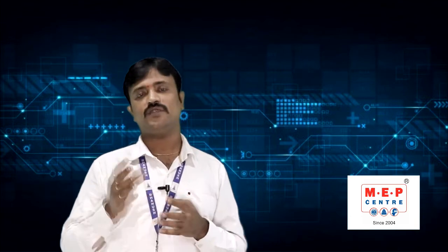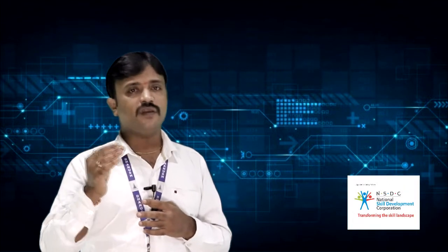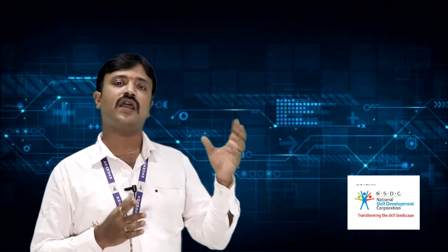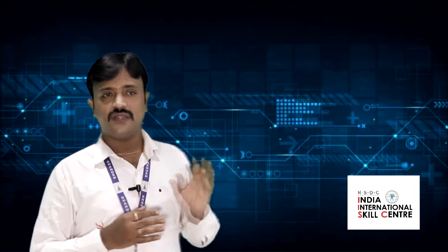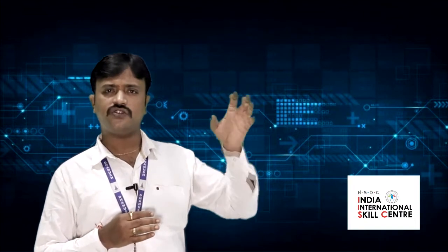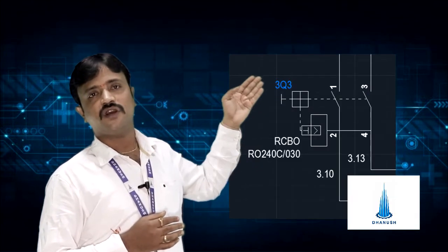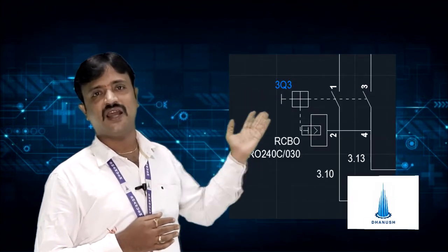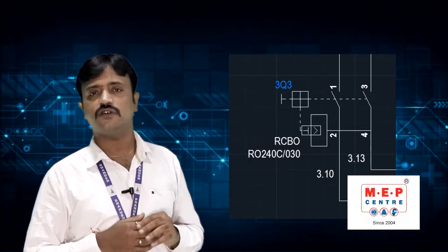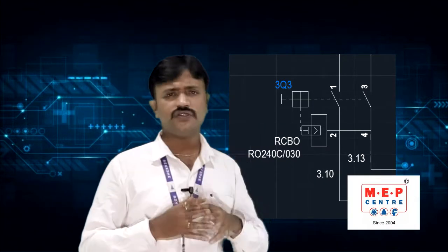What is tripping time? It means that the circuit breaker needs to trip within a particular duration. So we need to calculate that time and set it on the circuit breaker so that the circuit breaker will trip in that second. That is about the tripping time. So these are the overall calculations related to the circuit breaker. And you can see the circuit breaker technical denotation, how it is really represented, with the type of the circuit breaker, ampere rating and fault current, as well as the tripping time which the circuit breaker takes to trip. This is about the circuit breaker.